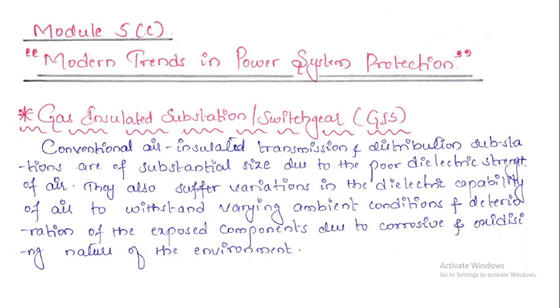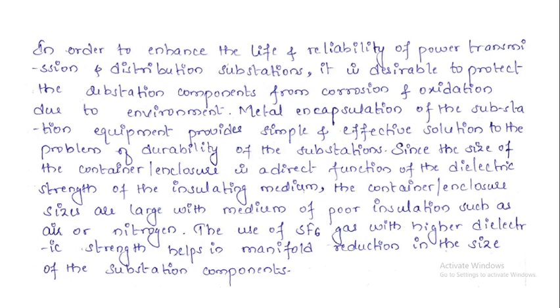Because of this corrosion and the oxidizing nature of the environment, these substations face difficulties, and we can't expect reliable operation from these air insulated substations. In order to enhance the life and reliability of power transmission and distribution substations, it is desirable to protect the substation components from corrosion and oxidation due to the environment. As I have already mentioned, as these air insulated substations are directly exposed to the environment, there is a problem of corrosion and oxidation, which may give rise to a decrease in the life as well as the reliability of the system.